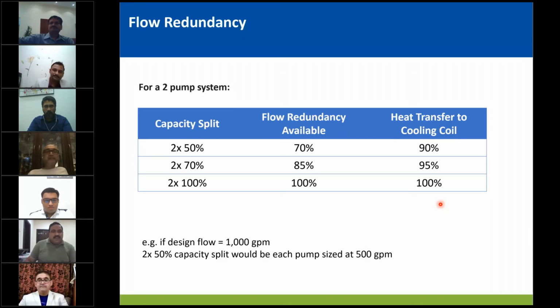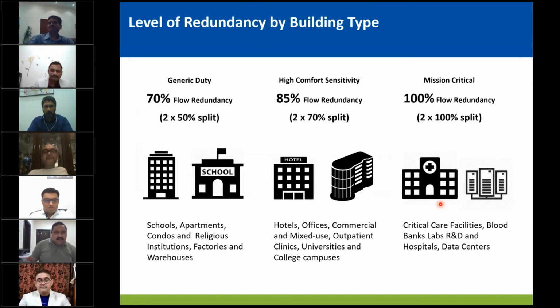Yeah, thank you very much. The other question is from Mr. Nixon. He wants to ask that as you told that there is no DPT installed in the chilled water pipeline for ramping the VFD up and down, if there is a pressure drop in chilled water pumping and the VFD needs to ramp up, then instead of analog, how will the system sense the pressure and the current in this system?